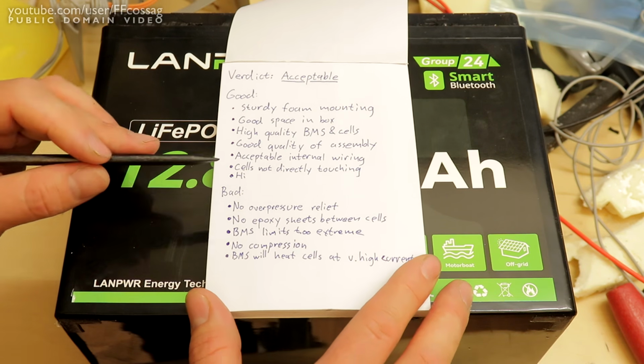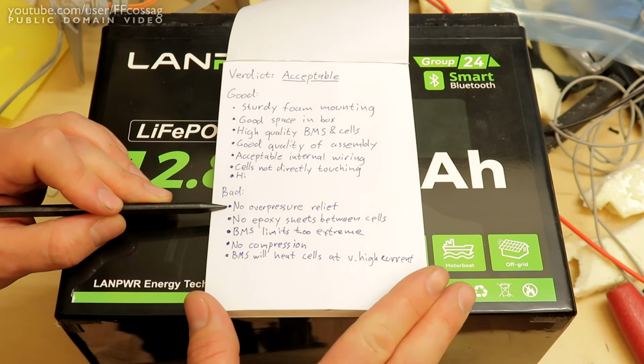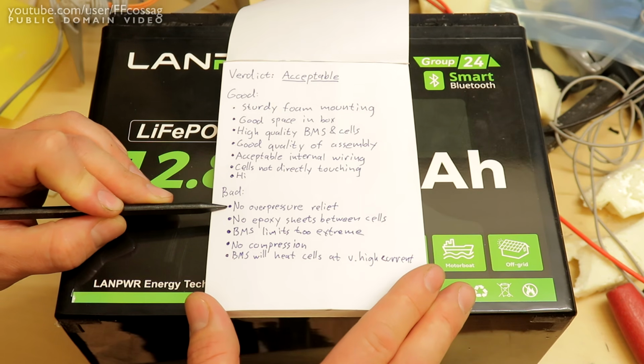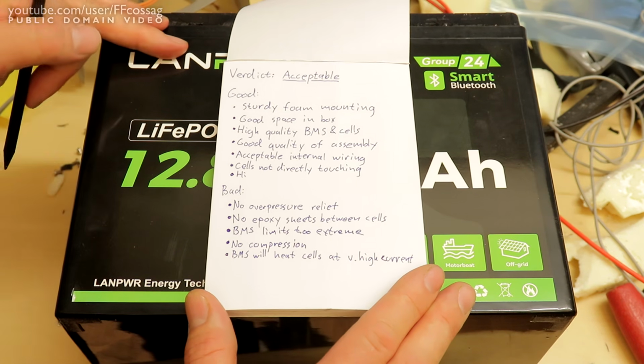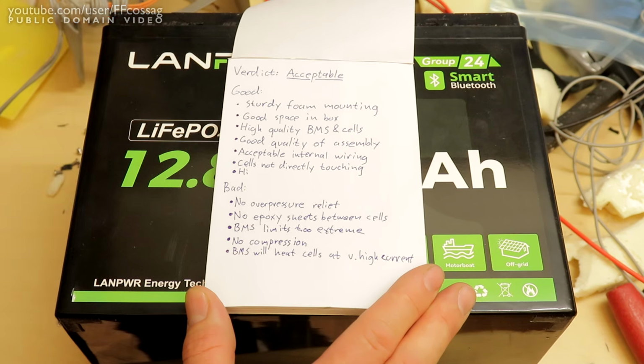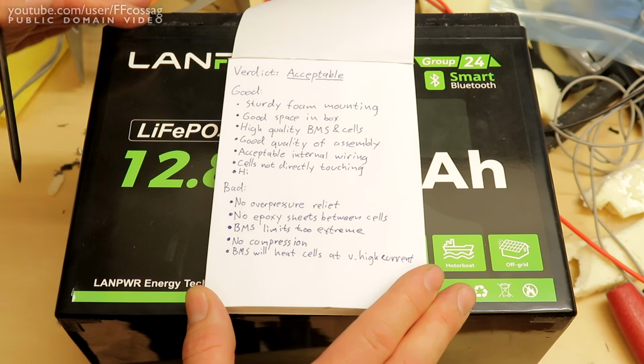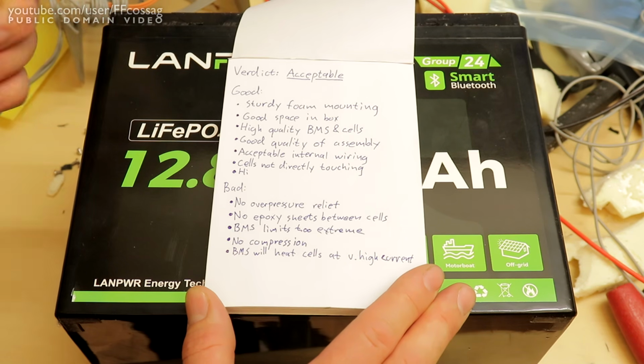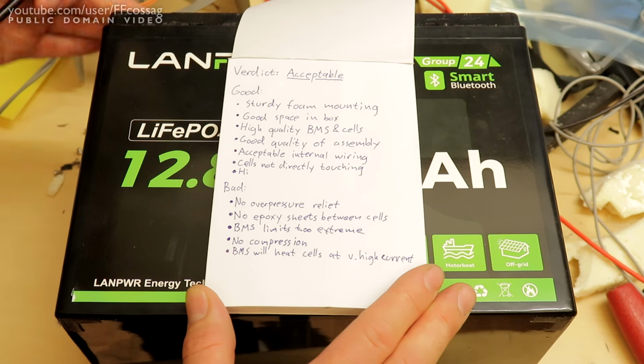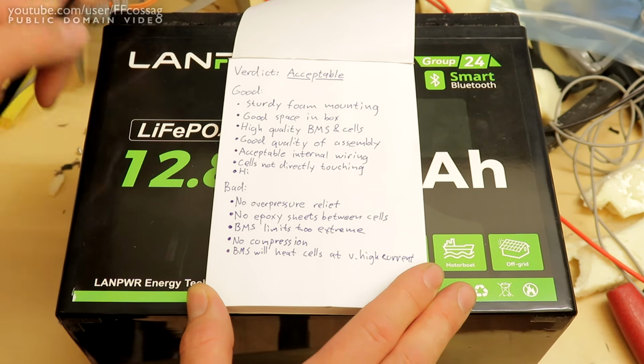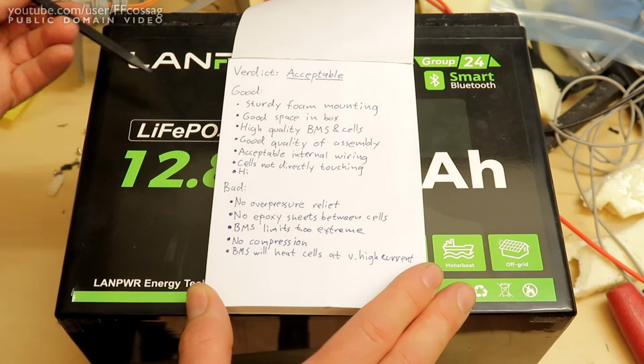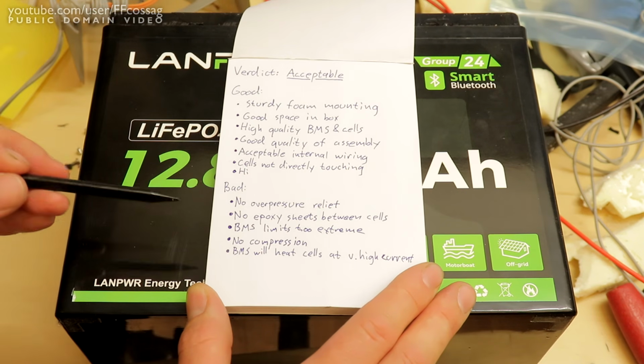The bad: no overpressure relief on the box. If a cell vents, pressure is going to build up until something pops. You want to see some kind of breather, some kind of overpressure relief. That also means it's impossible to vent expanding gases anywhere. If this goes, it's going to go where it sits, which is not ideal.